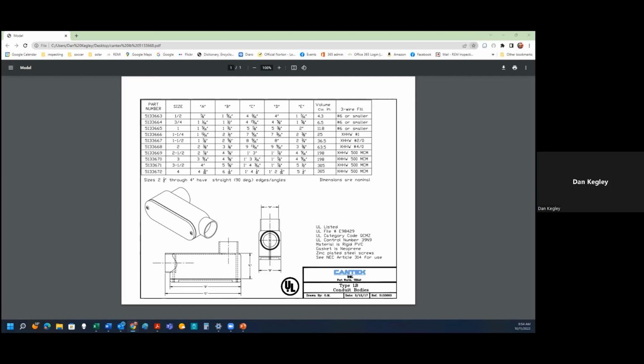It just says if it is explosion proof, you have to use explosion proof fittings. Gotcha. So if we use the NEMA 4X, the NEMA 4X is actually a vapor tight, dust tight environment when you use those seal offs, those seals, and those kinds of things. But it's not explosion proof rated or anything. Gotcha. But it should try to mitigate those gases from building up in there and that kind of thing. All right, 4X.